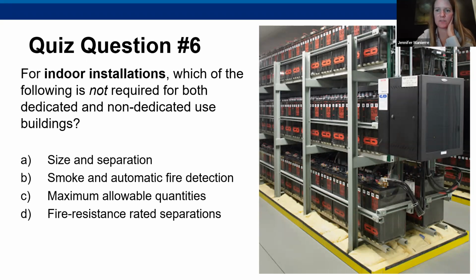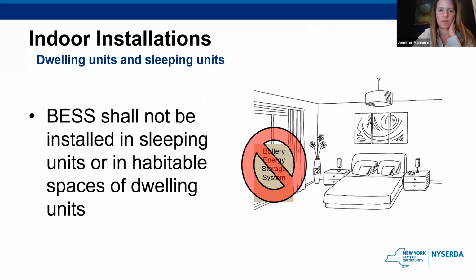But yeah, dedicated use buildings may exceed the maximum allowable quantities requirement. Sort of a no-brainer, energy storage systems should not be installed in sleeping units or in habitable spaces of dwelling units at all. We've talked about this, but when a battery system fails, it is likely to release toxic fumes. That is obviously not very good for a human to be around. So they should just never be installed in these areas where people are going to be hanging out, especially sleeping.